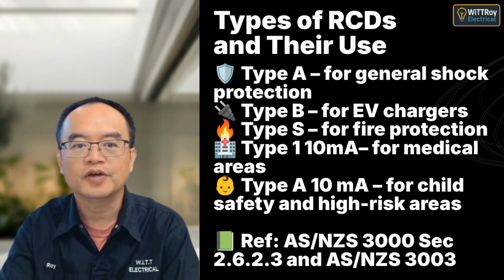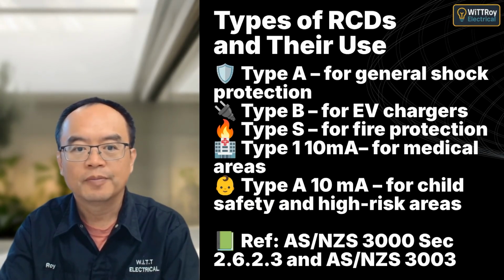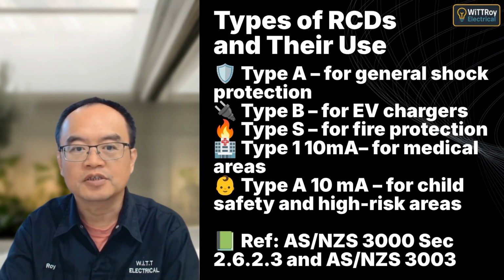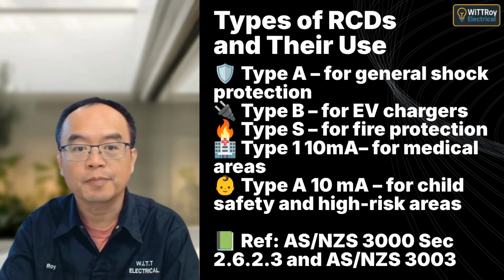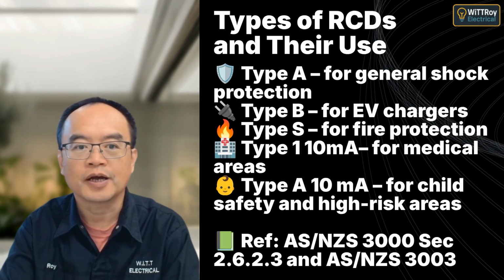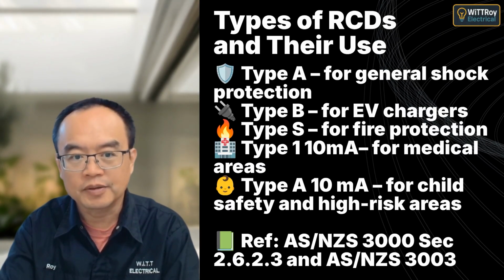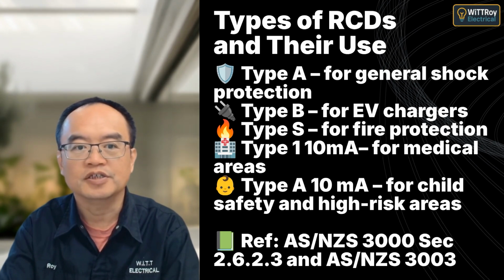There are different types of RCDs for different needs. Type A is standard, Type B is for EV chargers, and Type S is fire rated. Medical areas must use Type 1 10 mA RCDs, not Type A, and 10 mA RCDs are needed in child accessible areas.